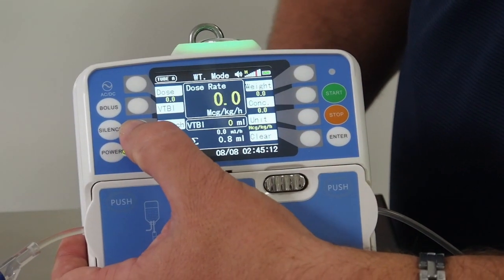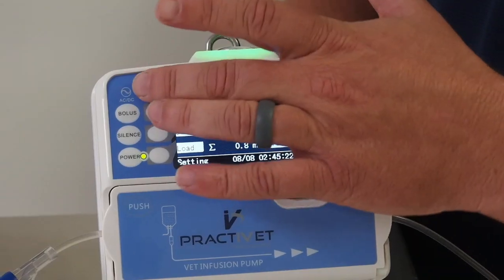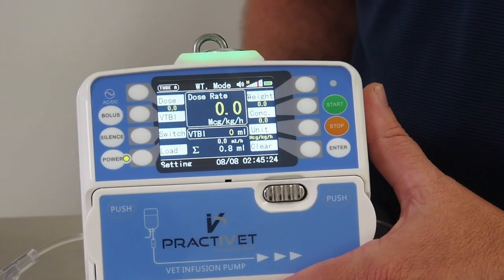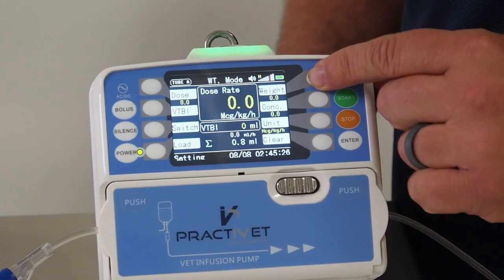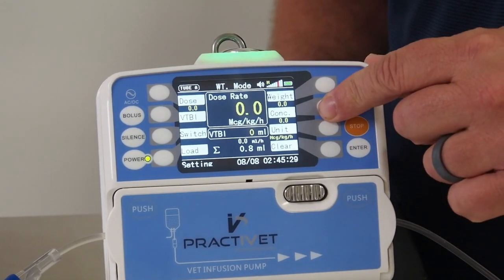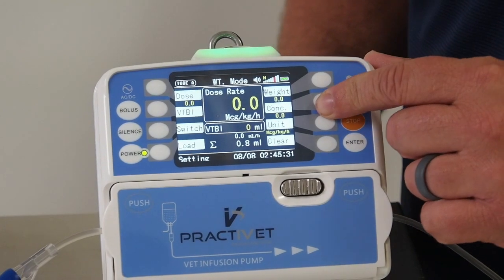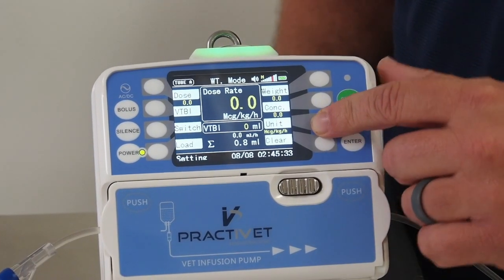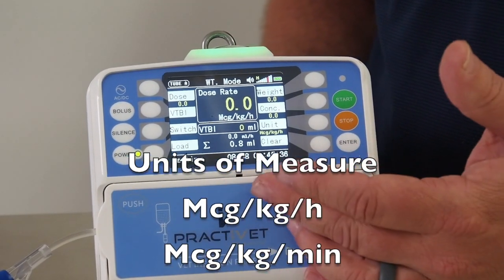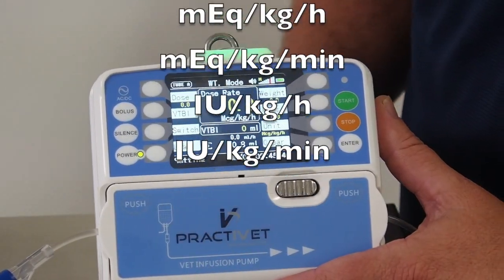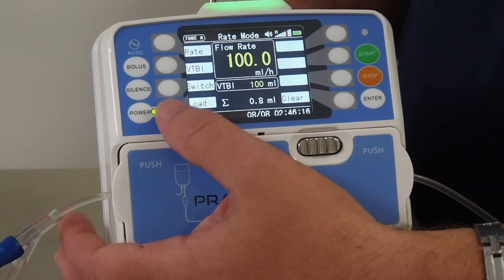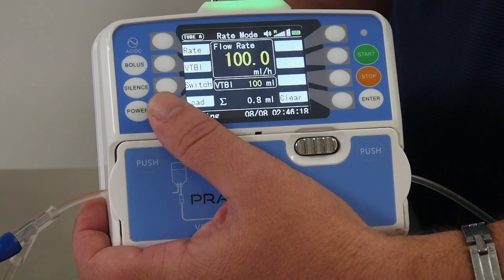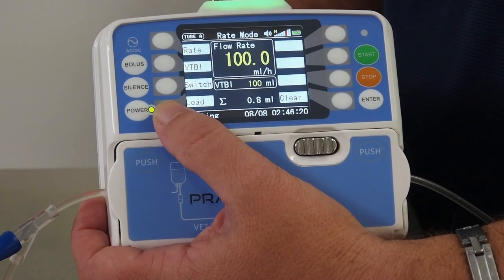You also have a dose rate. This is where you can set the dosage of the drug that you're administering. You would set the weight of the patient, the concentration of the drug in the bag, and the units such as milligrams per kilogram per hour or milligram per kilogram per minute, or many other options that they have available. And then you would start. The load soft key is going to load the last prescribed dose into the system.